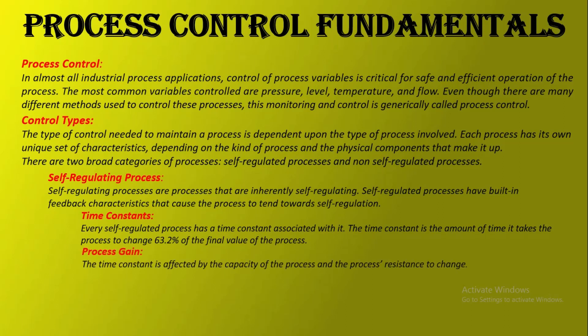The time constant is affected by the capacity of the process and the process resistance to change. The larger the process capacity, the longer the time constant. The more resistive elements in the process, the longer the time constant. Next, we will look at dead time.